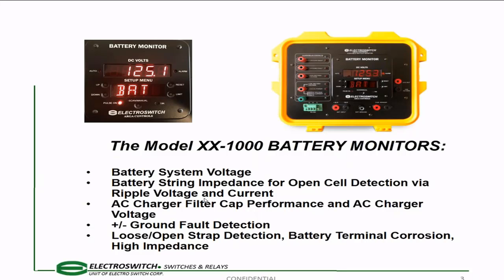It provides for monitoring the impedance of the system, open cell detection via monitoring of ripple voltage and ripple current, and depending on what's happening with your impedance, it's going to be an indicator to go back and check your battery systems. If you go back and check your battery systems and everything's fine, then the next thing we'll do is lead you to go check the AC filter caps, because they're probably degrading. Recently a utility found out that that was the exact issue. Positive negative ground fault detection, and loose open strap detection, battery terminal corrosion, high impedance is associated with monitoring of impedance.